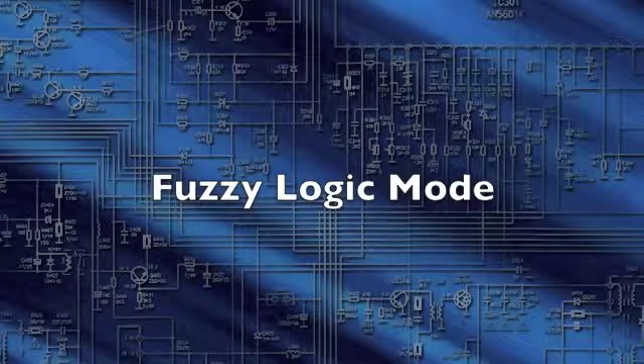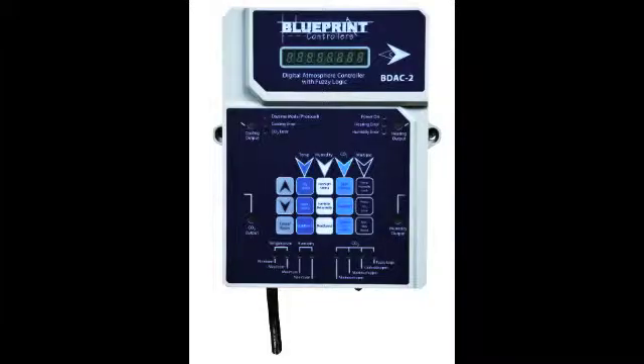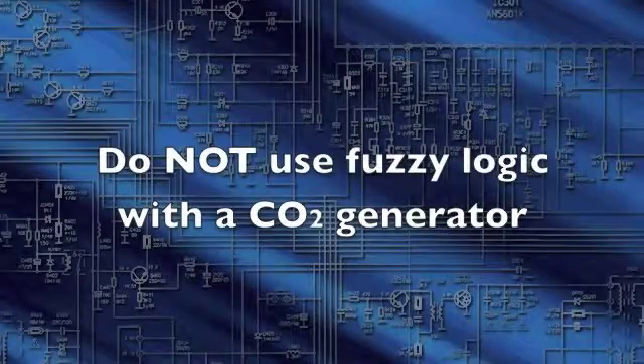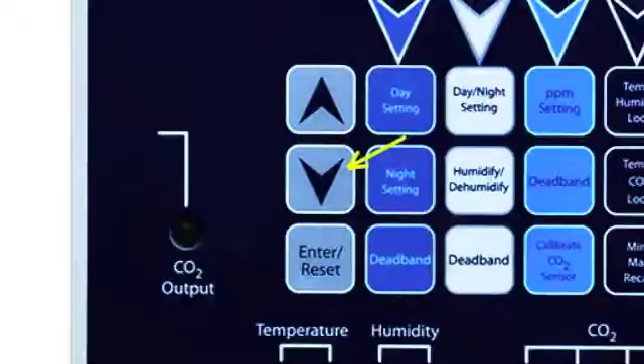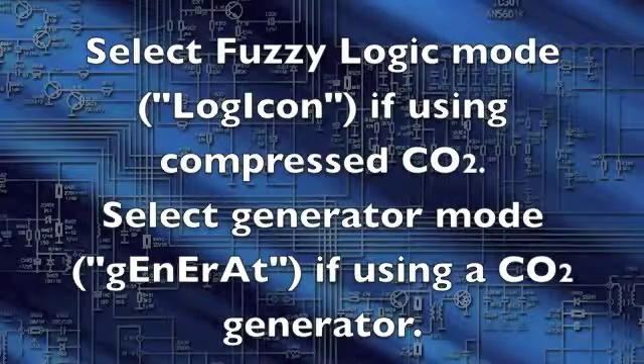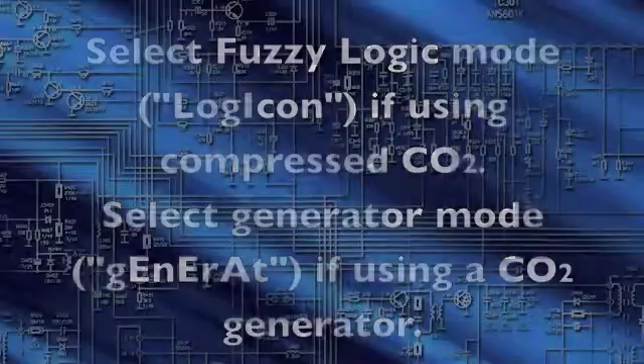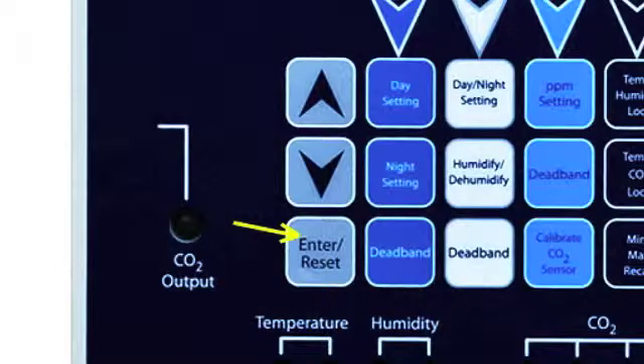Fuzzy Logic Mode counters rising or falling CO2 levels by quickly activating the CO2 solenoid valve, allowing CO2 levels to be controlled more precisely. This function can be used only with compressed CO2 — do not use Fuzzy Logic with a CO2 generator. Hold Enter Reset for 5 seconds to activate or deactivate Fuzzy Logic Mode. Use the up and down arrow buttons to choose between Fuzzy Logic Mode if using compressed CO2, and Generator Mode if using a CO2 generator. Press Enter Reset to accept the new setting.